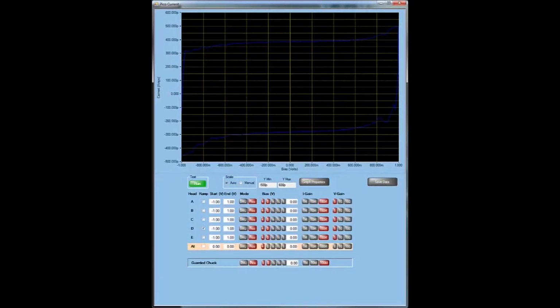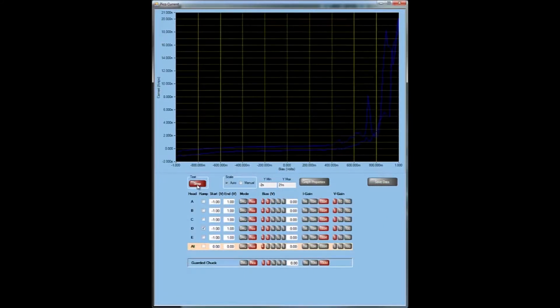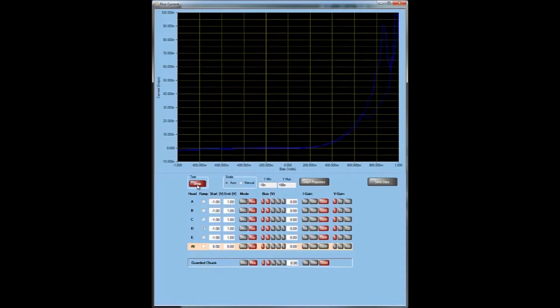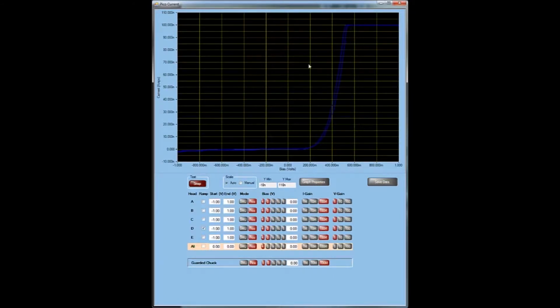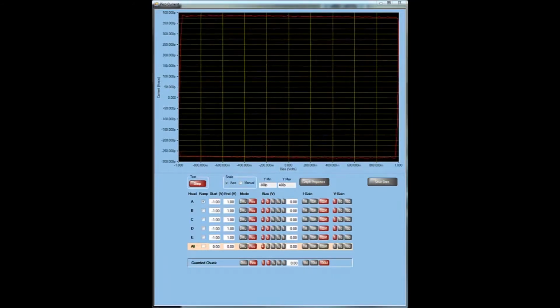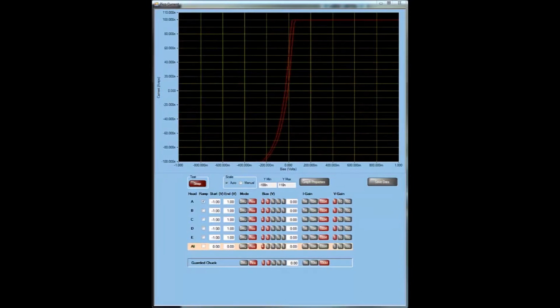The picocurrent tab in Multiscan is used to monitor the contact at the surface. Running -1 to 1 volt ramps on the tips tells the user if the probes are on the correct contacts and how good the contact is. The more current the probe tip pulls, the better contact it has.